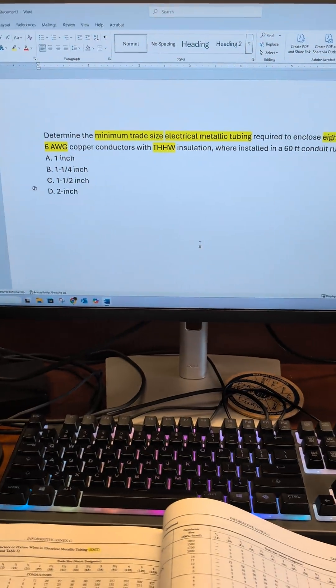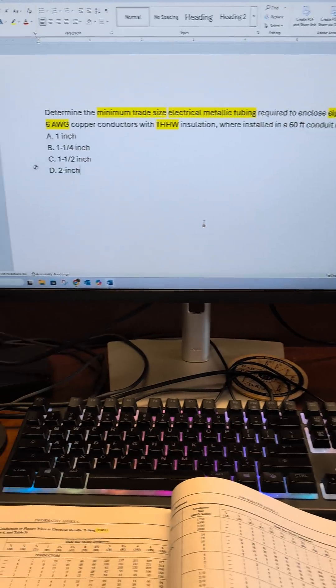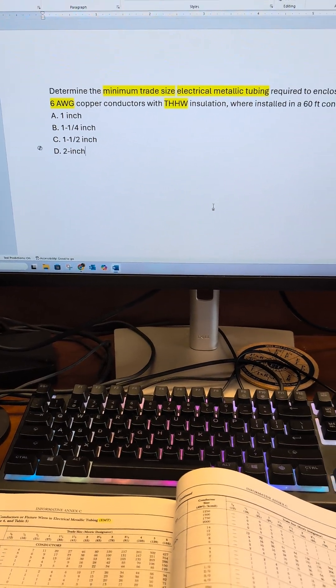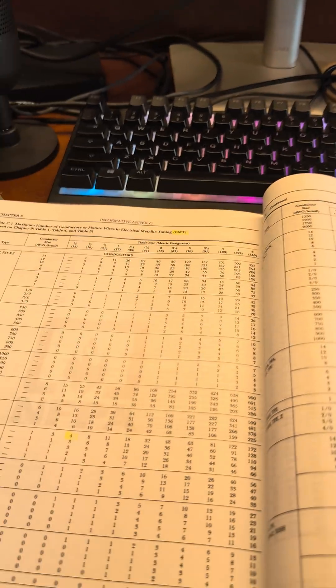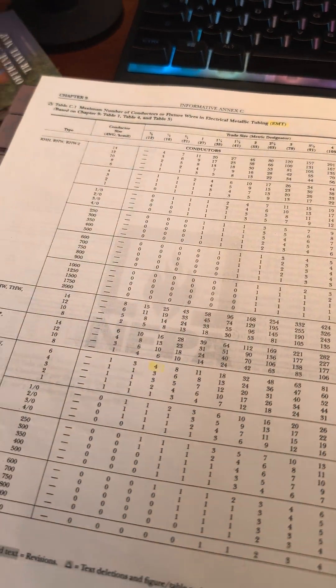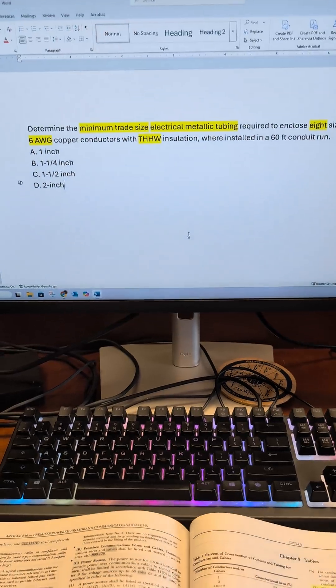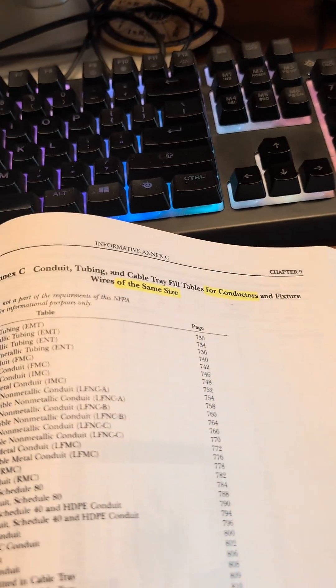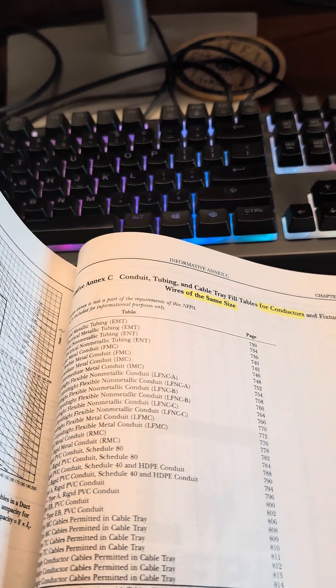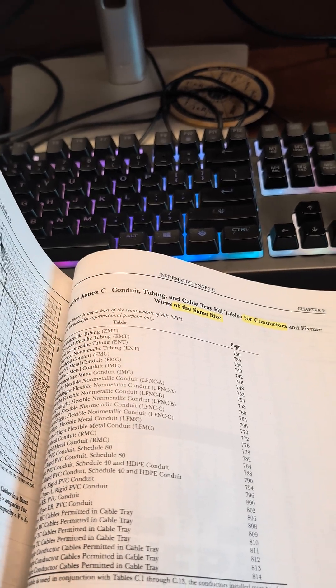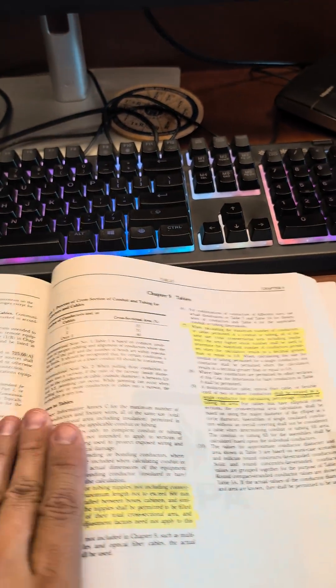We know we're trying to find EMT for 8 number 6 THHW insulated conductors. We used Annex C1 to find the answer previously. But what if these wires are of dissimilar sizes? Remember, the very key phrase in Annex C is for conductors of the same size.